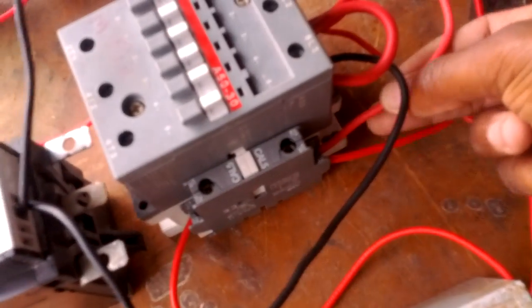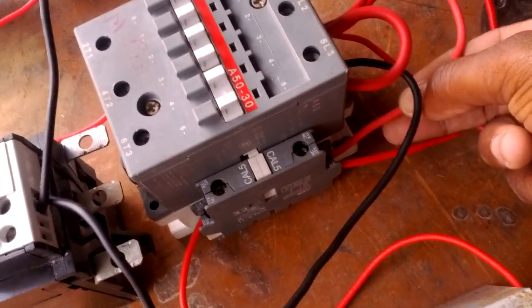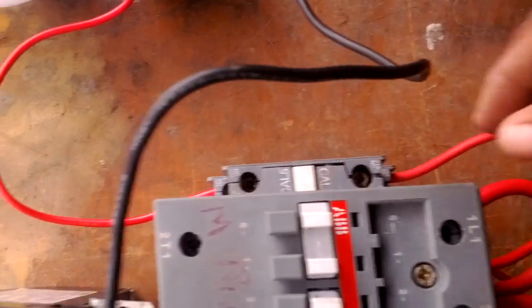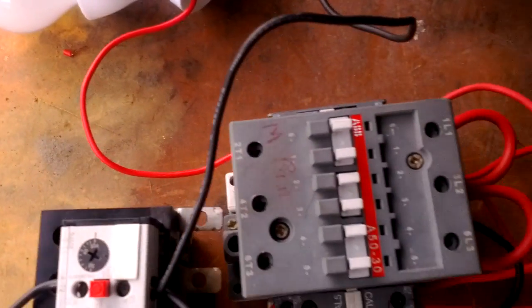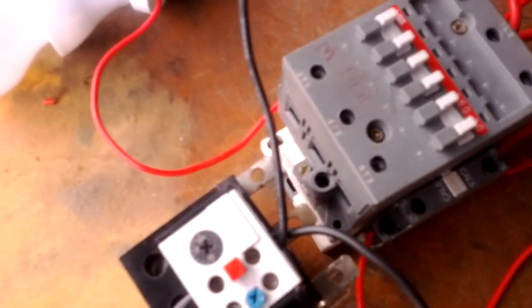So I took it from the back of an auxiliary on the holding circuit to a next auxiliary normally open. Remember that. And it comes out and goes to my cord for my light. That's the basic procedure, but I need you to be careful when you're doing this because you might end up getting the coil slamming in a way that the light will not turn on.